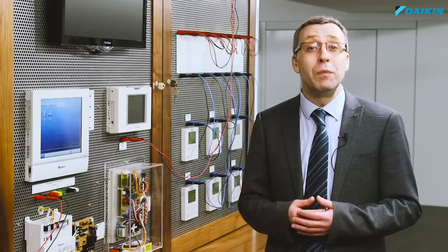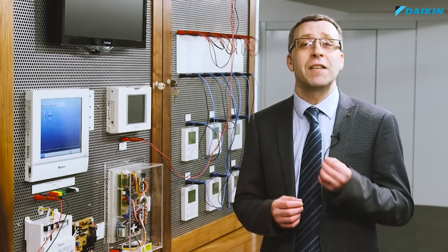Daikin's VRT, variable refrigerant temperature control, can be configured to suit individual applications and fine-tuned to precisely meet the needs of an air conditioned space. There are two main modes of VRT: fixed high sensible mode and automatic. Automatic allows the coil temperature to change in line with the room temperature and offers a range of settings so the system can be customised to match the building user's priorities.